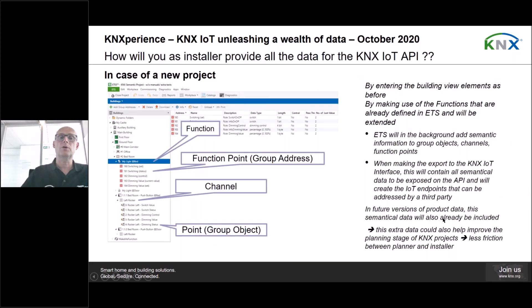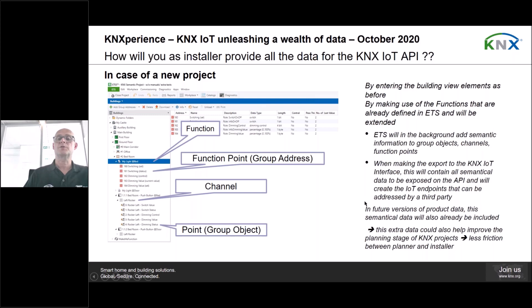As a first step, we will create a static interface based on OpenAPI, because there are widely available tools for that. As an installer, you will do your work as before — creating building view elements and a topology — but it is highly recommended to also make use of ETS functions. ETS will then, in the background, add semantic information on the group objects, channels, and function points. When you make an export to a KNX IoT interface, this data will already be included. In future versions of product data, manufacturers will also be able to add semantic information to their product data.